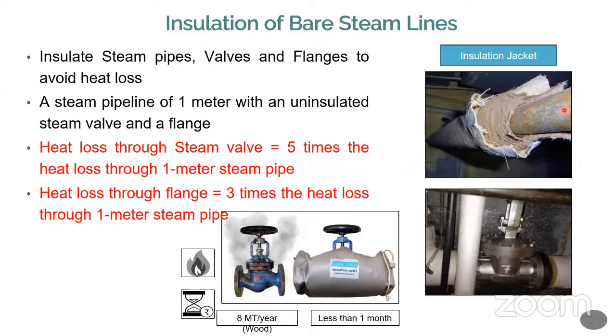Why? Because they say, sir, we have to regularly check the functioning of the valve, so therefore we are not insulating it. No, it is not correct. You need to properly insulate your valve and your flange also. That is why we have a separate system like this. You can see this is a detachable one. Earlier I had a pressure reducing valve which did not have insulation. Now it is covered with insulation, and it can be detached.